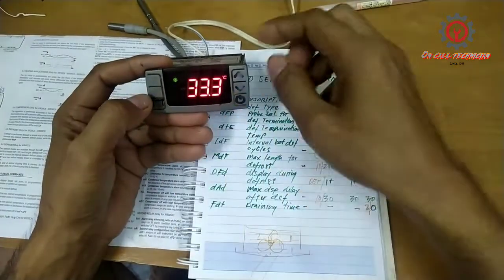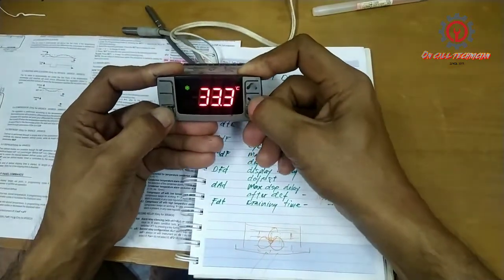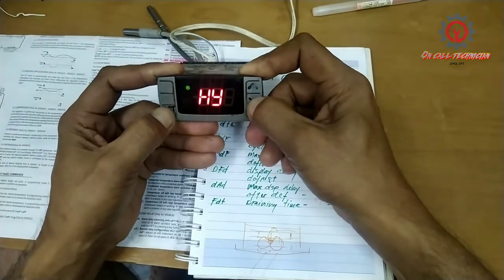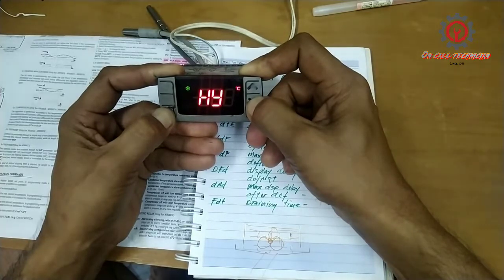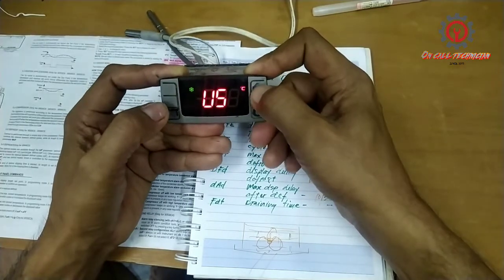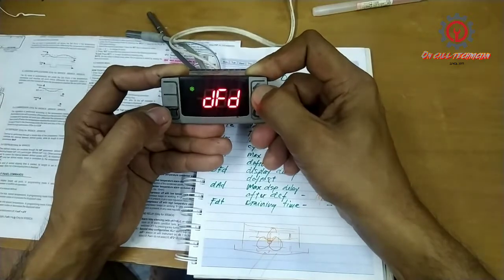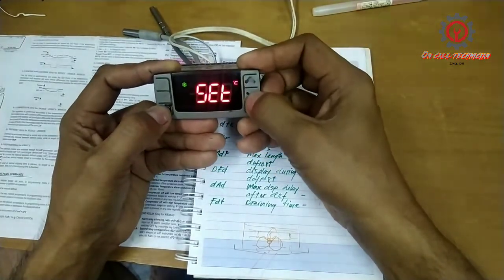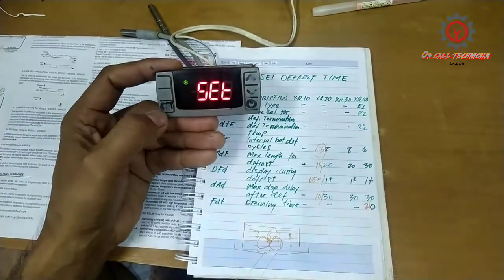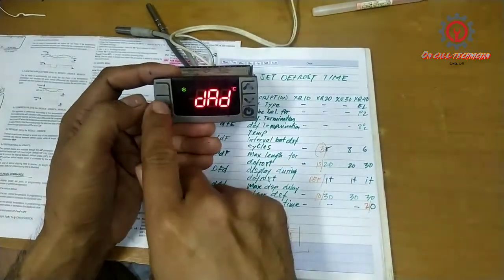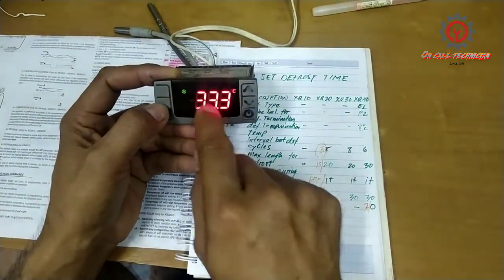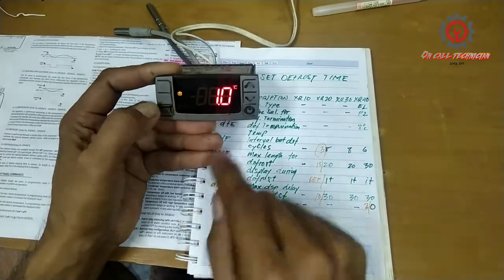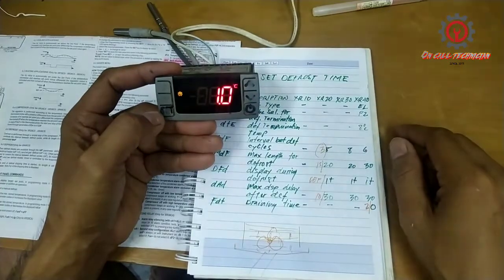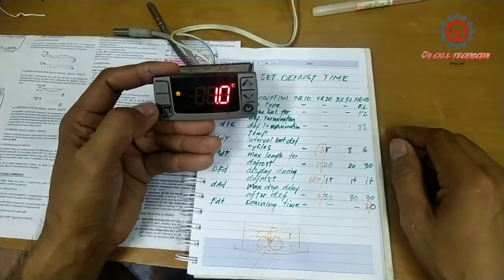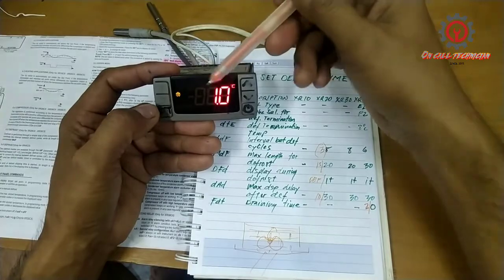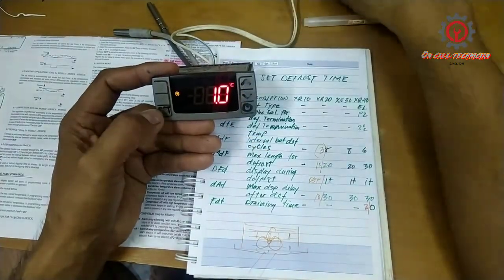And for example, guys, let's change that to DEF. And I'm gonna show you what if I'm going to manually defrost it, what is the type of defrost shown to the display. And let's locate the DFD. Okay, set. Let's choose this one, guys, is set point. If you want that to be selected, you can select that. Okay, but the moment I engage the manual defrost, set point. Okay, my set point is 1. It will be shown 1 degree Celsius here. Okay, so that is set. My set point is, this is a chiller. So let's end the defrost and on again.